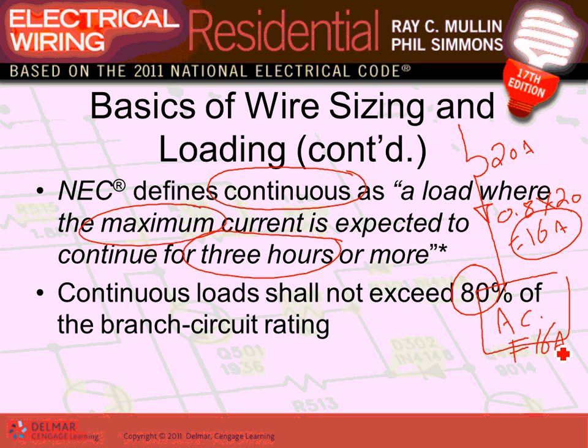That's exactly what the circuit breaker is. Safety. Because when you go higher than 90 miles an hour, controlling the car becomes tough, with some idiots driving around you too, so you're not alone. Same thing for that circuit breaker here. He's working with a bunch of idiots in that circuit breaker with him, right? So he starts heating up, and they start heating up too. So they create problems. That's what the derating is all about, 80%.